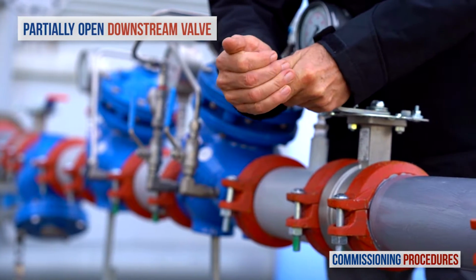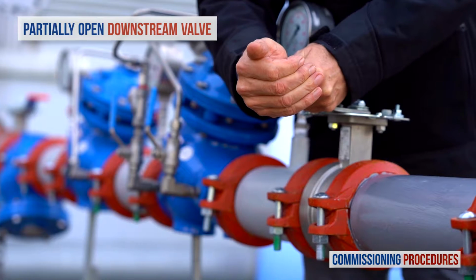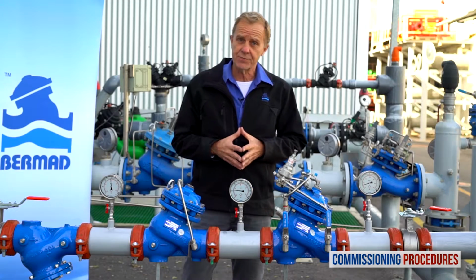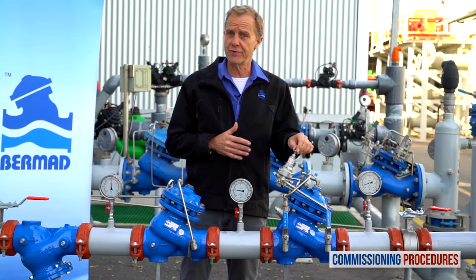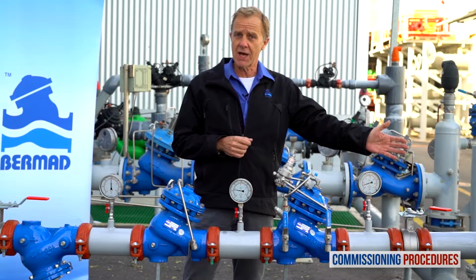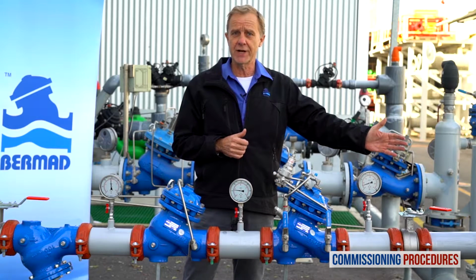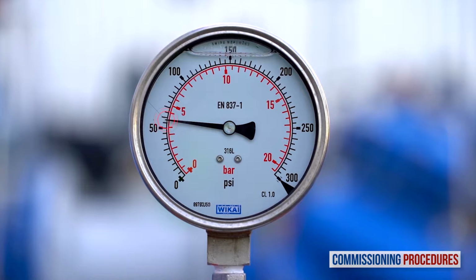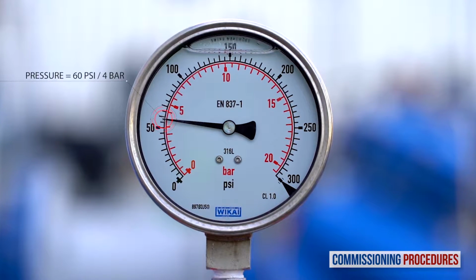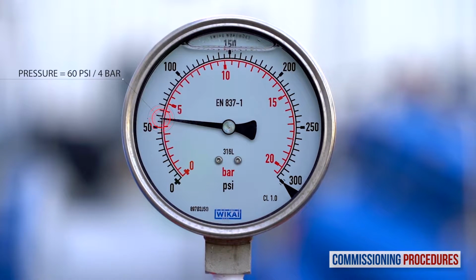Proceed by partially opening the downstream isolating valve. At this stage, if you haven't released the pilot adjustment screw for recalibration, the consumer's line connected to the station will fill in a slow and controlled manner. All you need to do now is to check that the downstream pressure is compatible with your requirements.